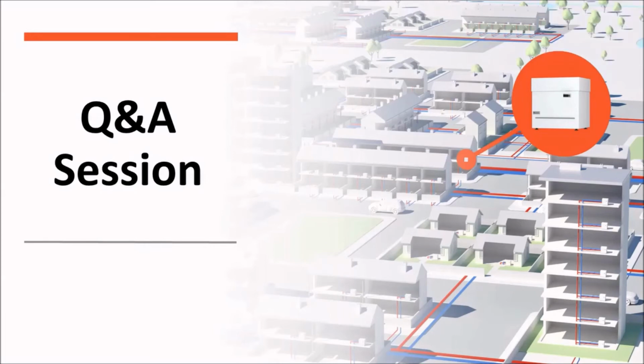How do the two ground loop systems, borehole and trench, compare in efficiency and cost, assuming land is available? Efficiency is the easy one because they're pretty much the same, but that's also artificial, because once we've decided on the type of collection system for a particular project, we design it to give a particular performance back to the heat pump - so we almost design out any differences between them. The horizontal ones, by their nature, take up a lot more space.